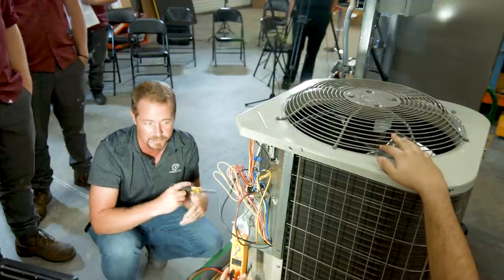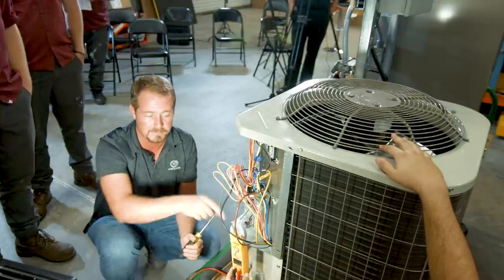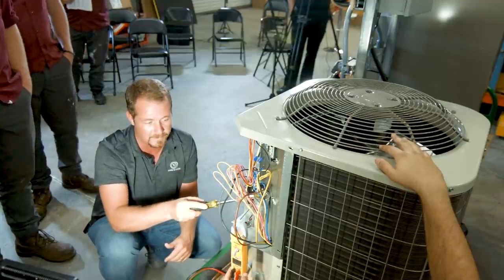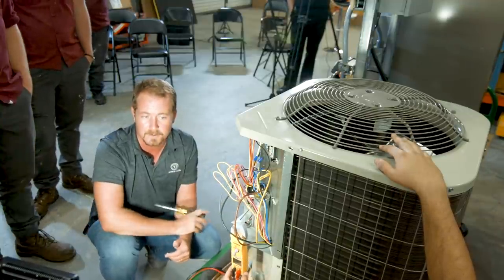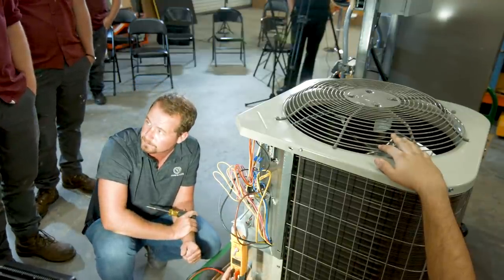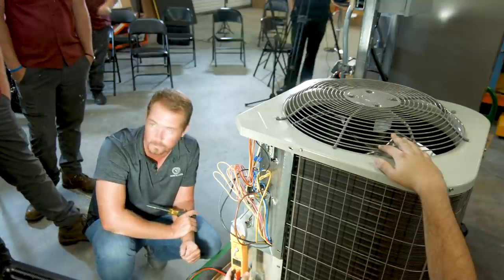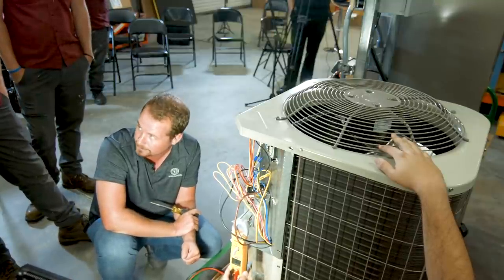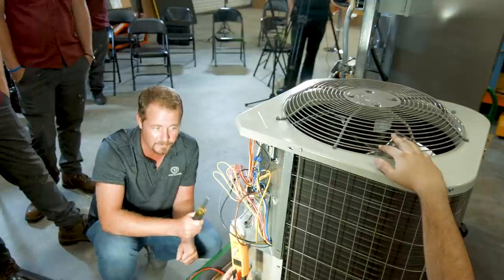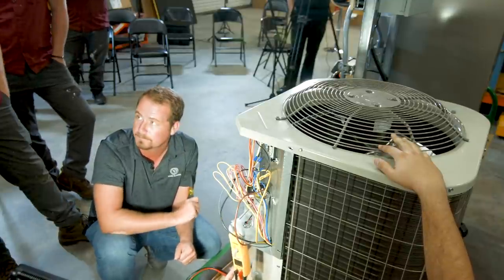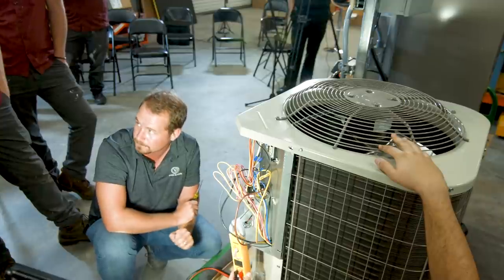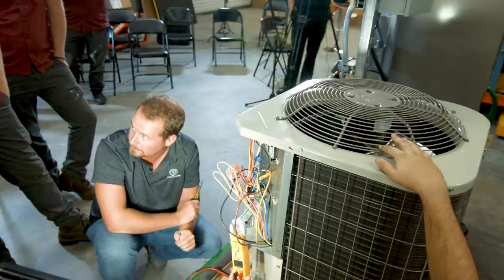But if you're not paying attention, a lot of techs would put these two wires on top. And if I put this wire over here, when would the crankcase heater run? When it's operating. When the unit's on, which is when you don't need it to run. And when it's off, it wouldn't run. So that would be silly. What happens if we put them both on the bottom? It'd be constantly running, all the time, whether the unit was running or not. That would also be bad.